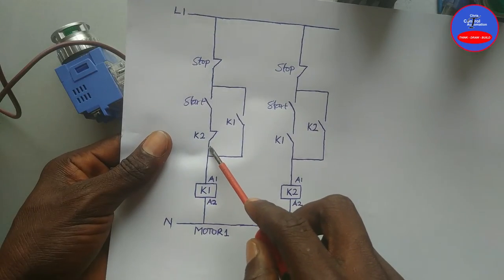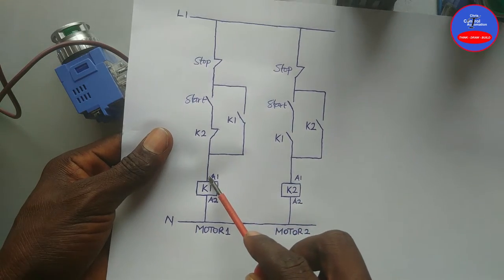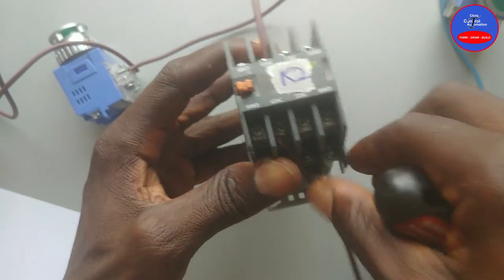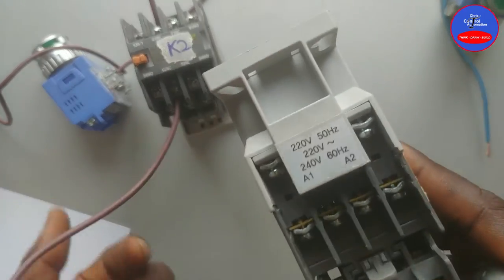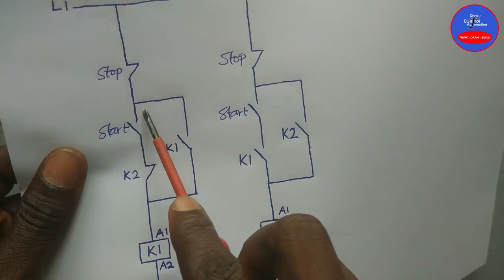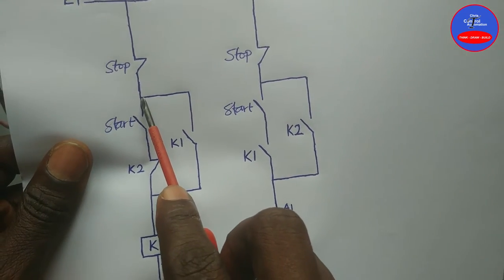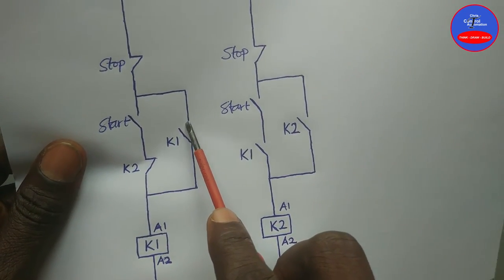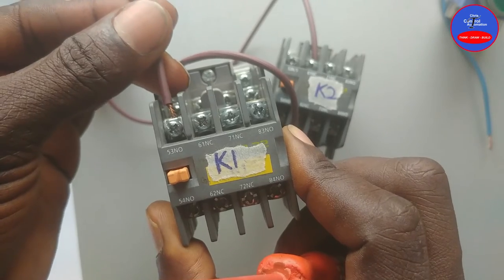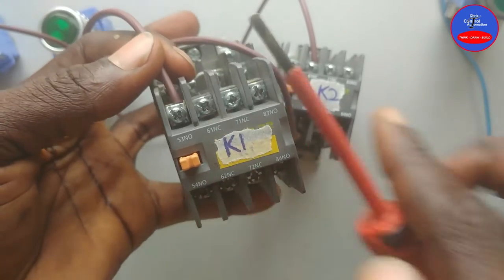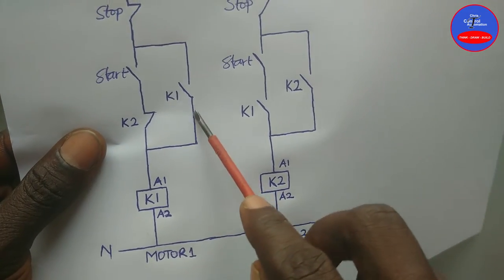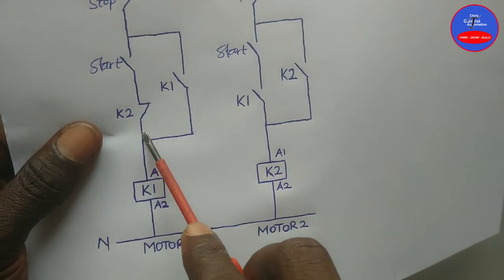From the other side of the start button it goes to one side of the close contact on K2. From the other side of the K2 close contact it goes to A1 of K1. We tap from the input side of the start button to one side of the open contact on K1, and we tap from the other side of the open contact on K1 to the K2 close contact.